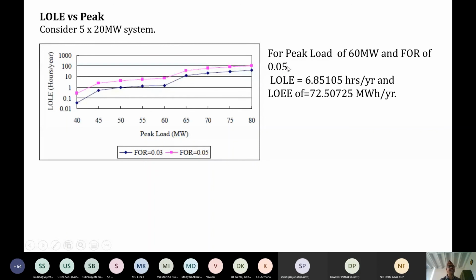You can see we increase the forced outage rate means there will be more forced outages of the generating unit. That means the risk index has to increase, and loss of load expectation is a risk index. Its higher value indicates higher risk. Similarly, loss of energy expectation is also a risk index. Its higher value means higher risk. Okay, so therefore, when this forced outage rate is 0.05, loss of load expectation and loss of energy expectation have actually increased. We can see here.